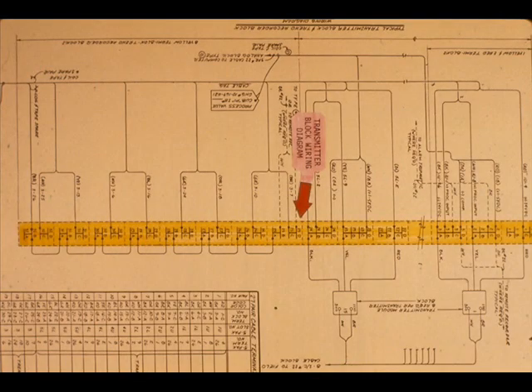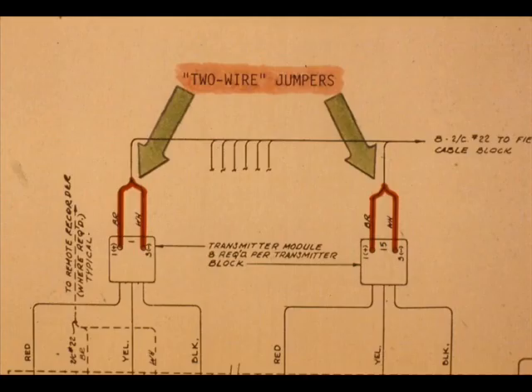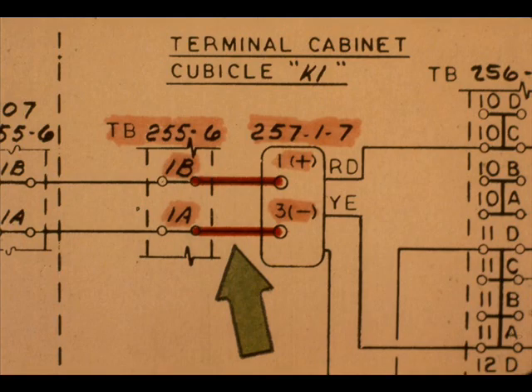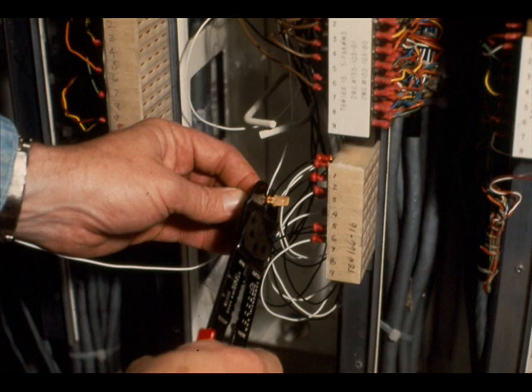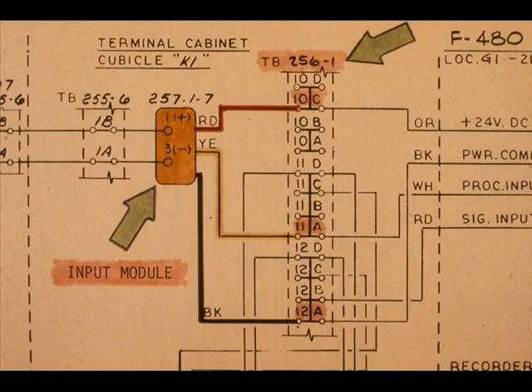This terminal block wiring diagram shows the interconnections between field cable block, input module, and the controller. It corresponds to the loop wiring diagram. This block is called a transmitter block. The wiring to the extreme right consists of 2-wire jumpers that connect terminals 1 and 3 of an input module to the field cable terminal block. Can you locate the jumper on the loop diagram? This is the jumper. It connects the input module to the field cable terminal block. Install and terminate the jumper as per the transmitter block drawing or loop diagram.